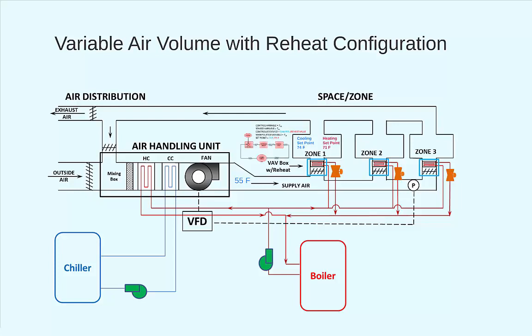For such situations, there are two approaches we can take to cut down on such energy waste. The first approach is actually quite simple, and actually it's done at a lot of the bases in the Air Force. We just remove the capability to provide cooling during the winter and remove the capability to provide heating during the summer. That is, we drain the chilled water lines for the winter and disable the boilers in the summer. That way, we won't be paying to cool the air to 55 degrees Fahrenheit coming out of the air handling unit, only to heat it up again at every VAV box downstream. This process of draining chilled water lines might also be required to prevent freezing of the pipes that don't contain any glycol.